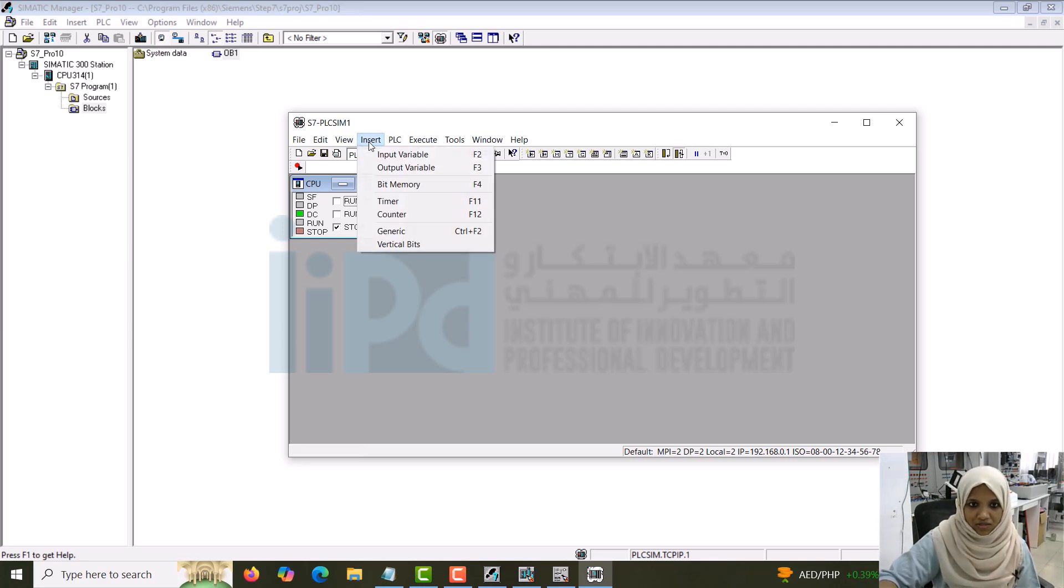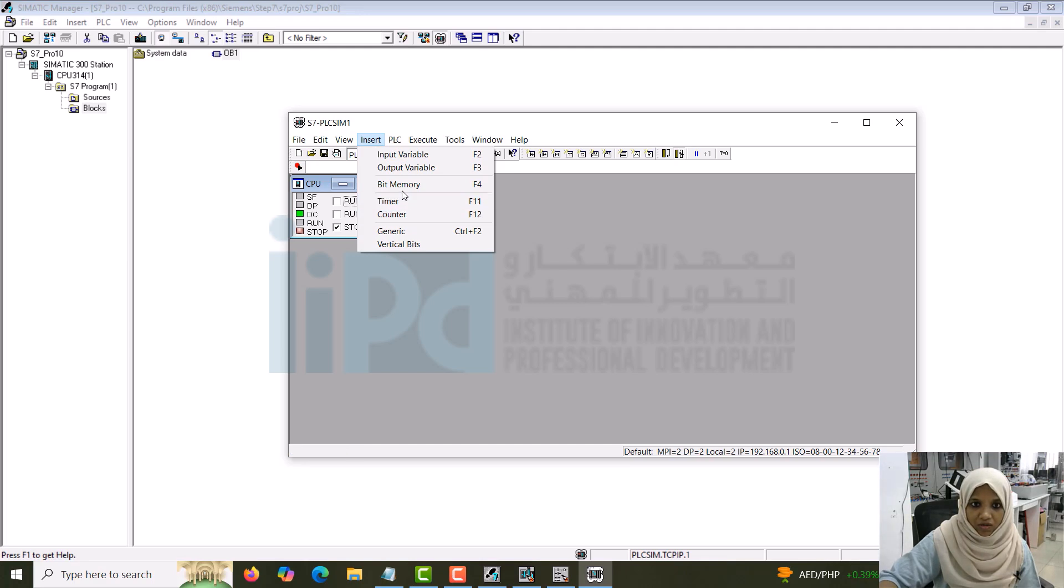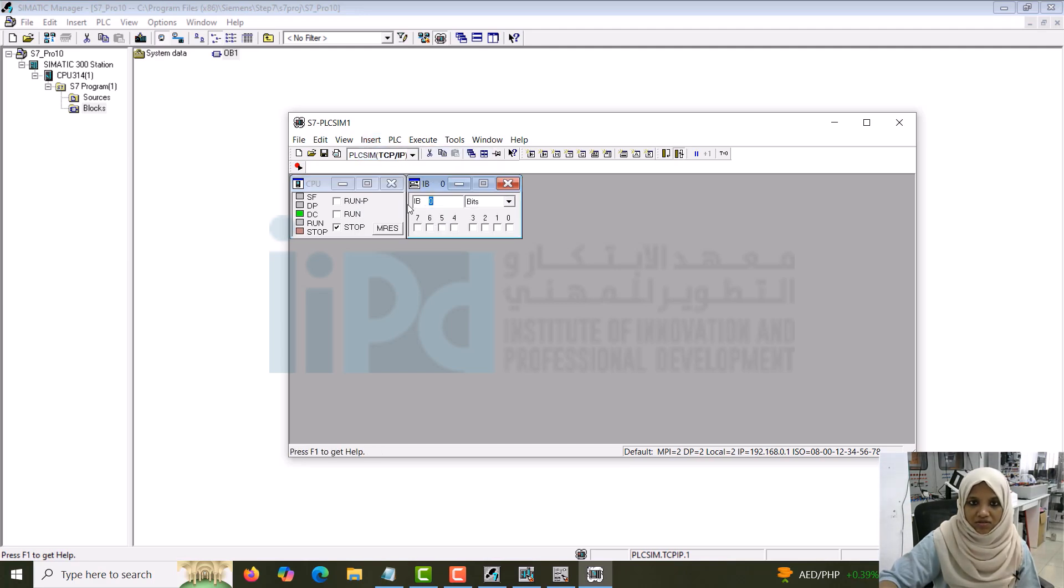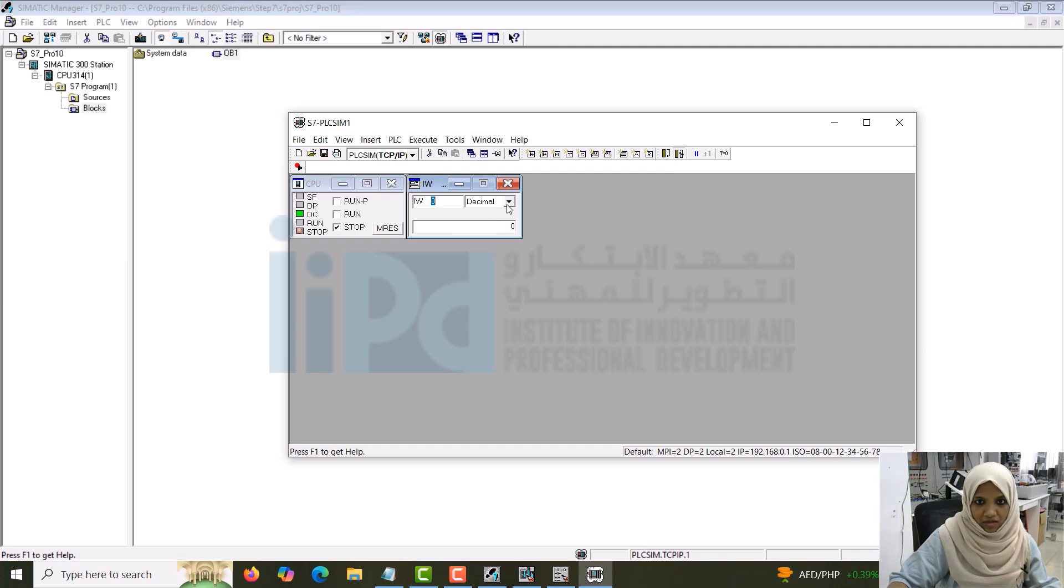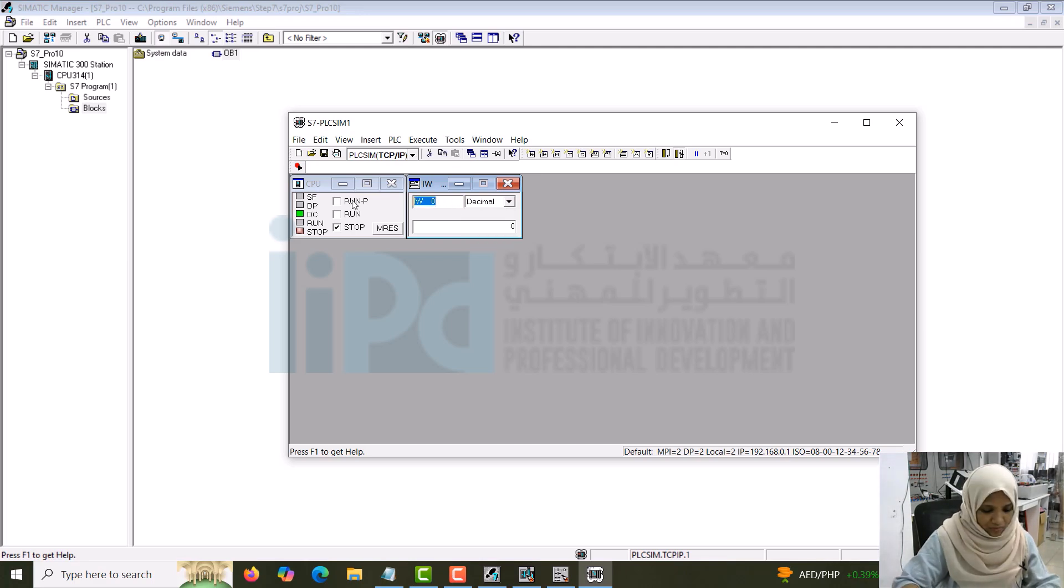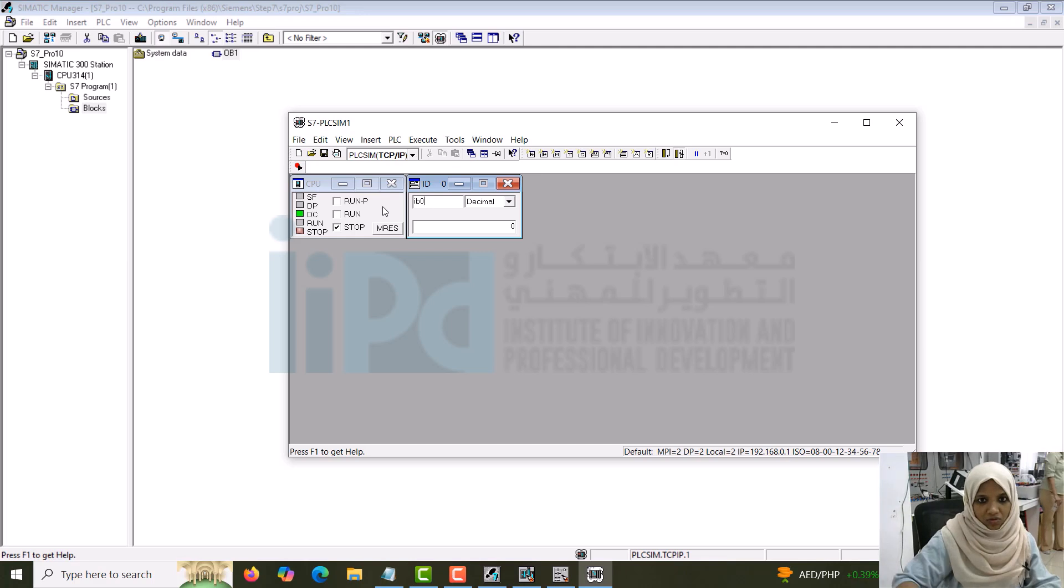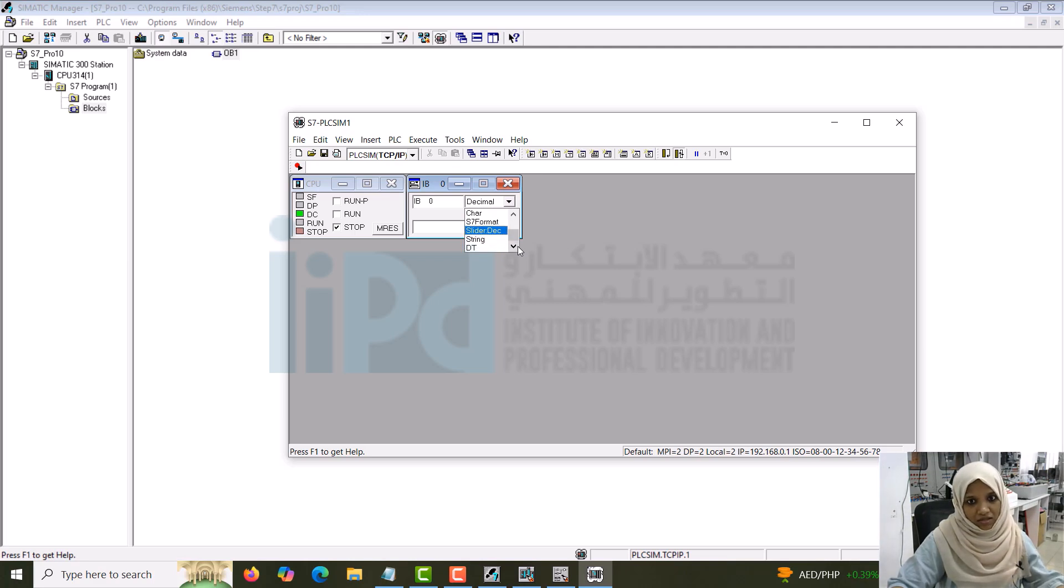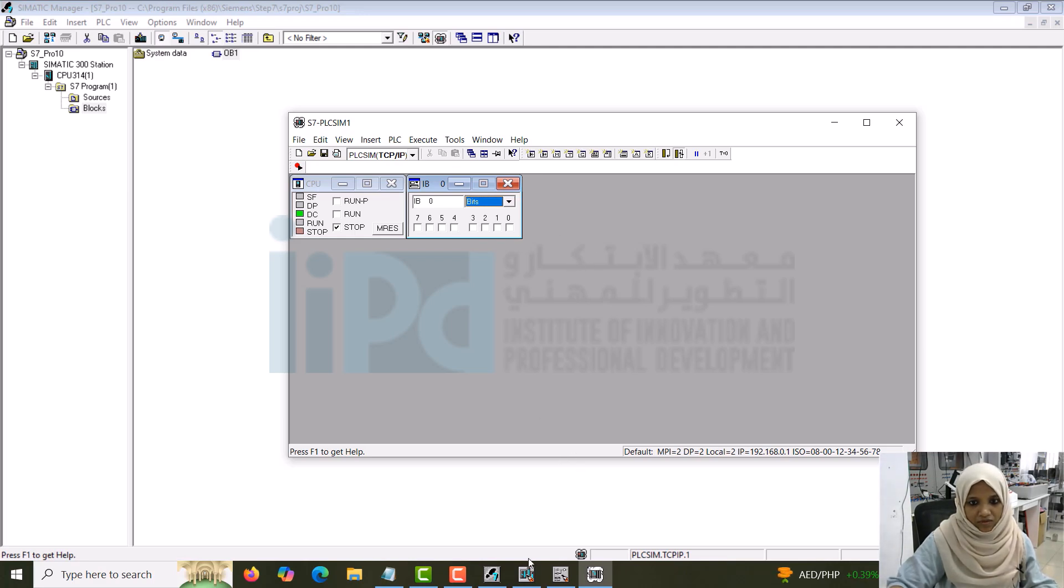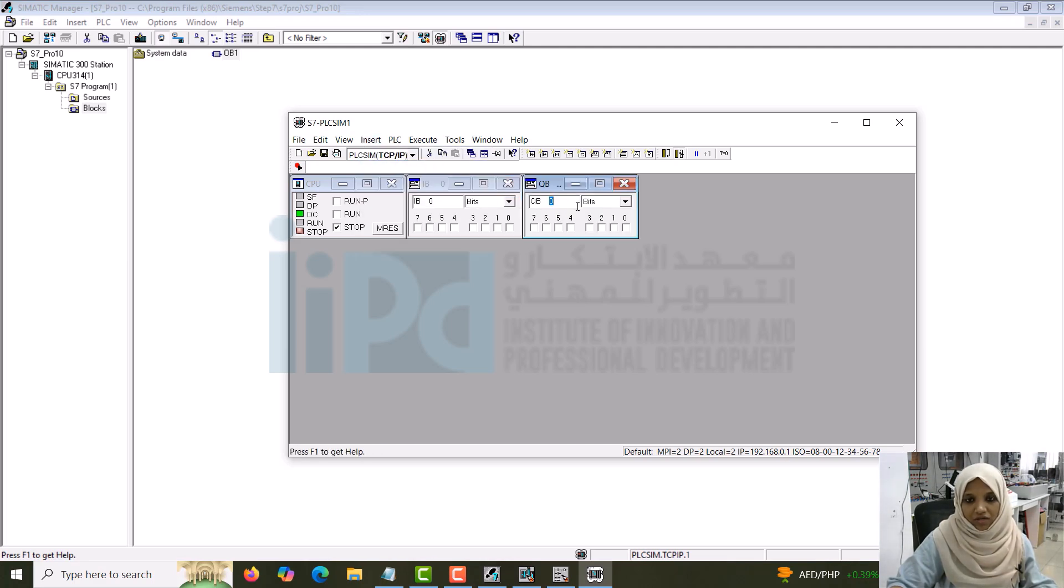In that case, go to the insert. Here you can see input variable, output variable, bit memory, timer, counter, whatever you need can be seen here. I will go to the input variable. You can see IB0. In that, all the 8 bits will be seen. If you want to change the representation here, you can give it as IW0, it becomes word. And if you want to change the format here, that is also possible. If you want to make this to ID0, double word, that is also possible. Now what we can do is IB0 is the byte. This has to go to the bits format. Generally, you can turn on and turn off everything. Once this is done, you can insert an output variable also. My output variable also will be of 0th byte because we gave the address as I0.0 and Q0.0.